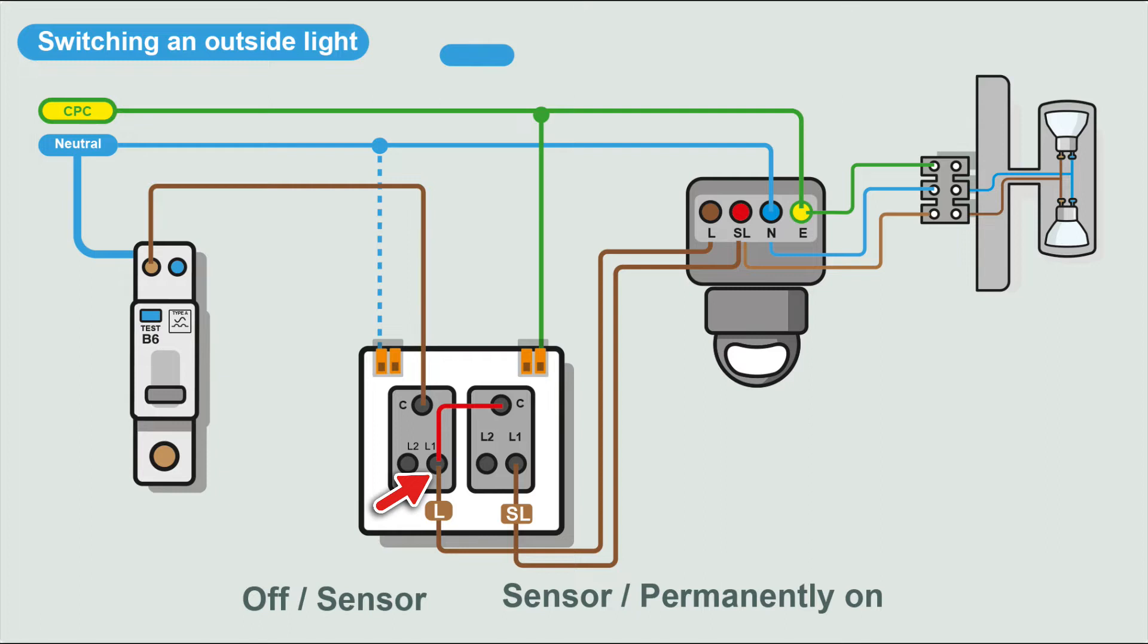And you'll have your sensor function. And as you can see, when the first switch is on, we're taking the feed onto the common on the second switch. And when we switch the second switch on, that'll take a feed to the switch live in the PIR, and you can have the light permanently on. So in this setup, you can have everything off, you can have it on a sensor so it automatically detects, or you can have it permanently on. So you've got good functionality there.